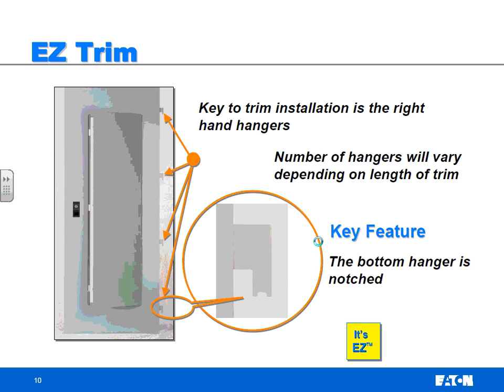Here's just a snapshot of it. The key is the hanger for the notch in the bottom of this trim. You can see the trim is just a solid piece. It's got no screw holes, nothing else on the front that's going to get in the way. Basically you take this trim, set the notch into the strip on the panelboard box, and the door can close itself, and all the pieces just fall into their associated notches. The door swings shut, you give it a quick lift and it drops right into place, and then it's got the normal lock on the front of the panelboard that all the other panelboards have to lock it out safely.